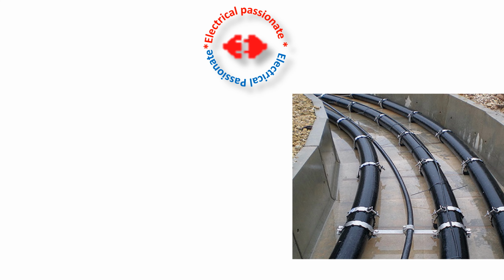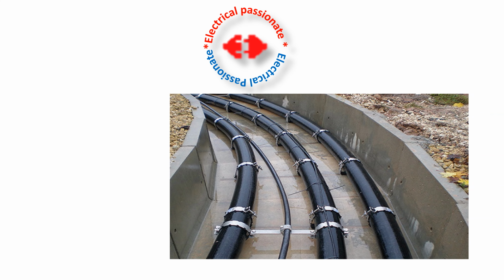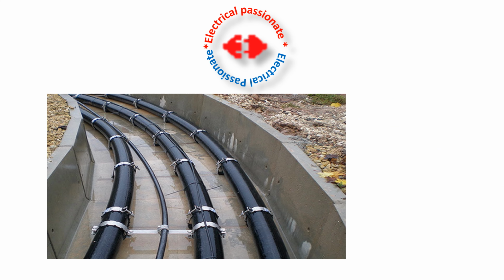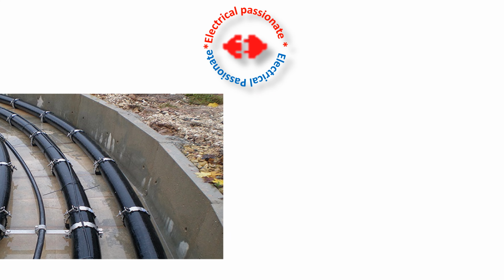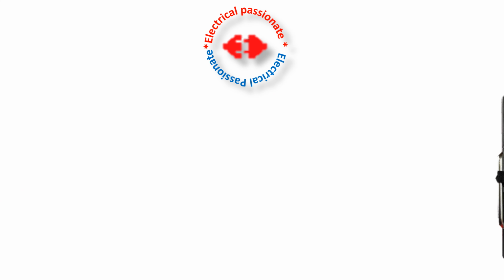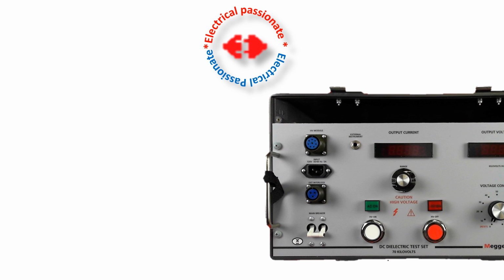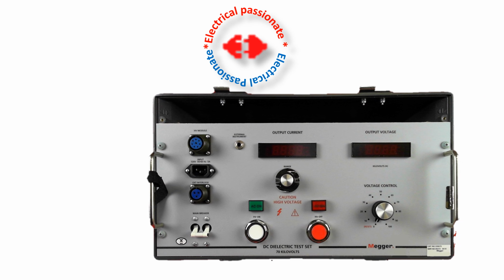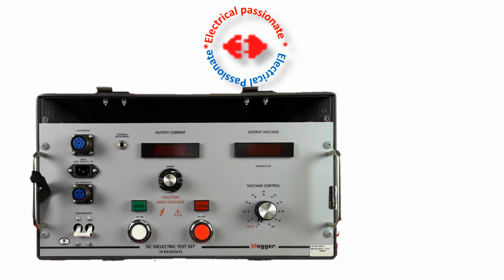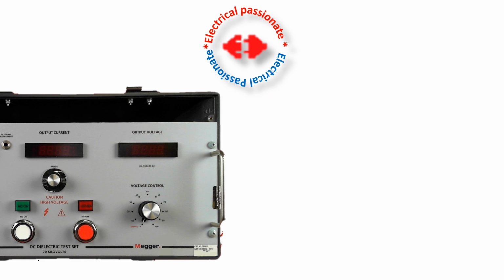Today we shall discuss the testing procedure of the high potential test, Hipot test, of an 11 kV XLPE power cable by applying high voltage for a short duration, 1 minute, by a testing kit to verify the dielectric strength or integrity of the cable.